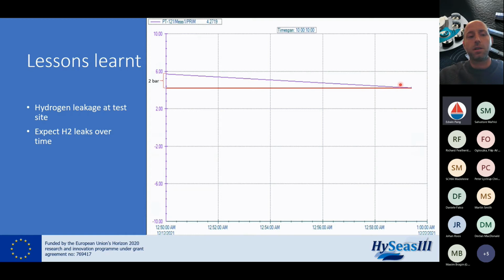Another one that we want to highlight is the leakage over time. What you can see here is a trend over 10 minutes from site with a closed system. These are closed valves on both ends of the fuel line, and we can see approximately 2 bars of reduction. We initially thought this was due to temperature changes, but the temperature during this time was quite stable. So it made us do a little more digging, because some of the gas sensors had actually detected this, but below the alarm limit. It was detected at around 200 ppm, which in some cases has caused a pre-warning, but it's not so high that it will cause a shutdown.